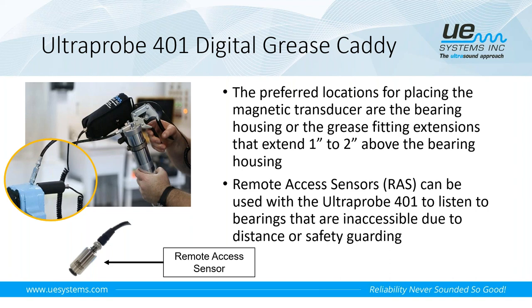Here's a picture of the remote access sensor. These are stud mounted or contact mounted sensors that will plug in directly to the grease caddy. We make these with cable lengths as short as 3 feet or as long as 100 feet. And again, it's a great way to listen to equipment that you normally don't have access to due to safety, or equipment that's just inaccessible due to distance. It's a safe way to listen to that equipment and still be able to apply grease to it, as long as you have those grease fittings extended out to where you can access them.